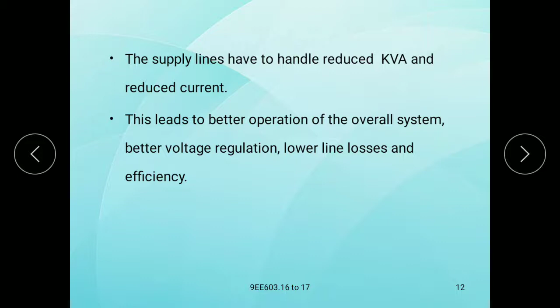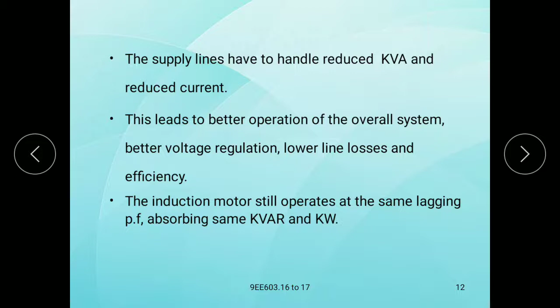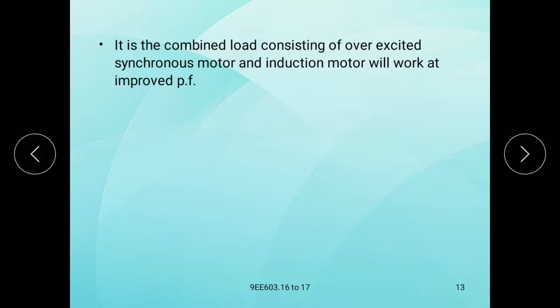This leads to better operation of the overall system: better voltage regulation, lower line losses and better efficiency. The induction motor still operates at the same lagging power factor, absorbing the same KVAR and KW. Here the combined load, consisting of the overexcited synchronous motor and induction motor, will work at an improved power factor.